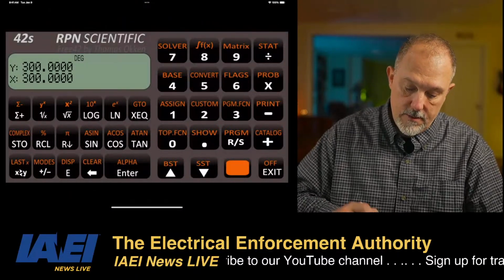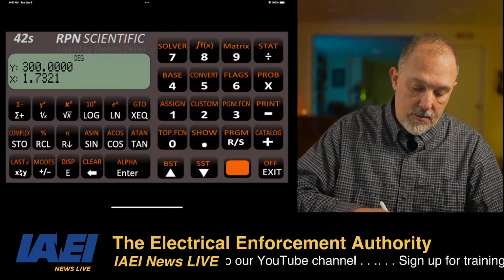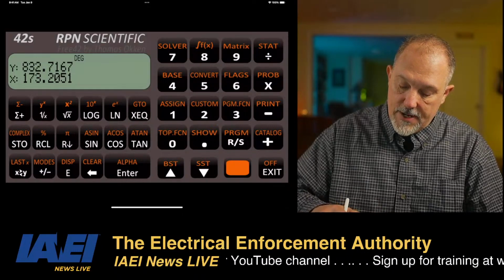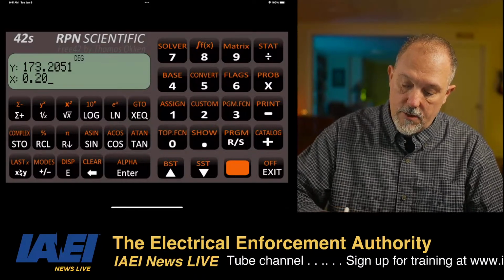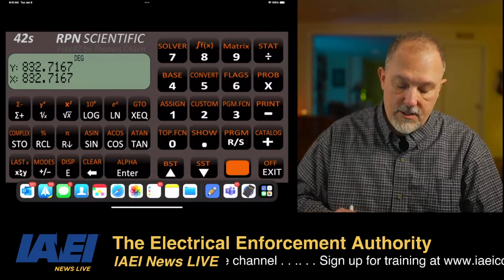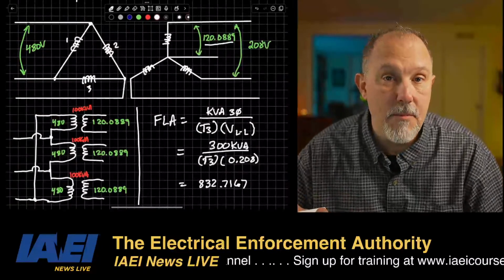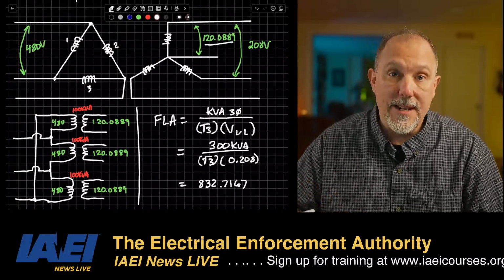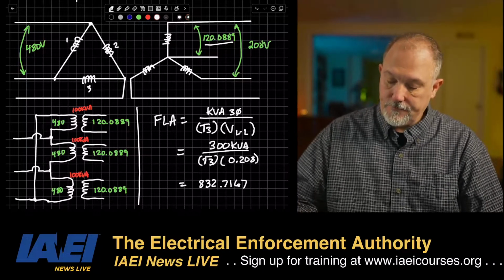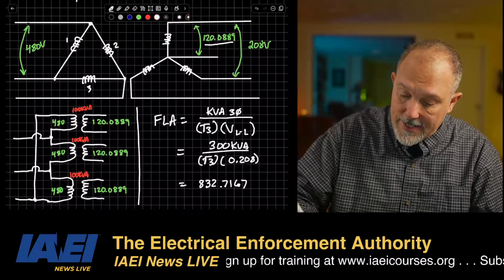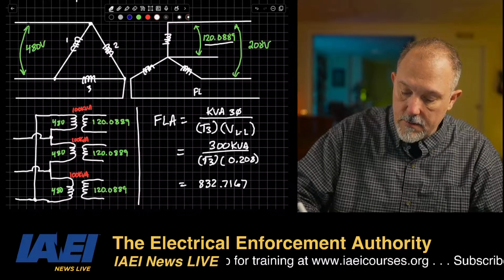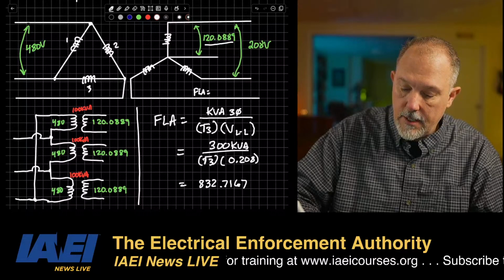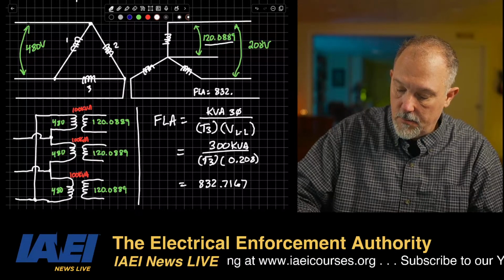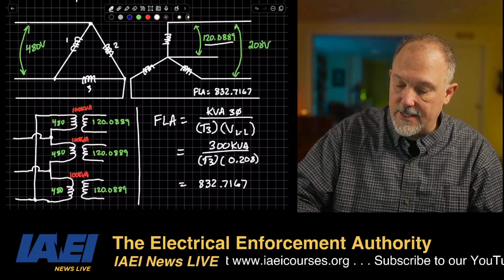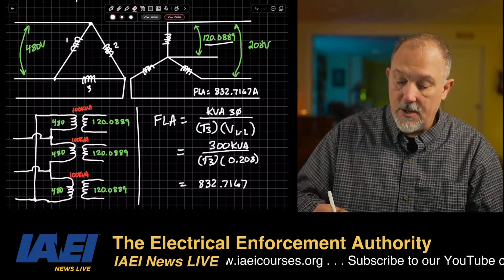300 divided by the square root of 3 divided by 0.208, 832.7167. I do my math twice because I can screw things up easily. Okay, so that tells me the full load amps is equal to 832.7167 amps on the secondary.